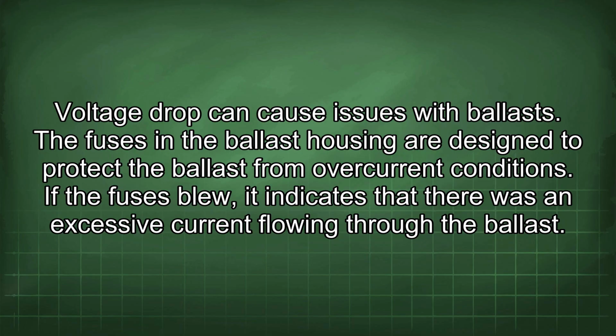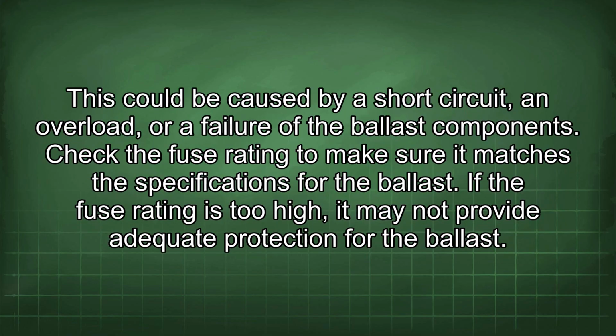The fuses in the ballast housing are designed to protect the ballast from overcurrent conditions. If the fuses blew, it indicates that there was an excessive current flowing through the ballast. This could be caused by a short circuit, an overload, or a failure of the ballast components. Check the fuse rating to make sure it matches the specifications for the ballast. If the fuse rating is too high, it may not provide adequate protection for the ballast.